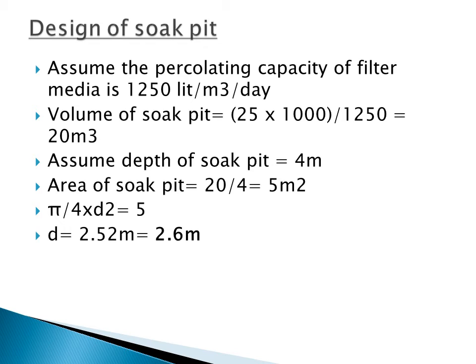The last part is to design the soak pit. You assume the percolating capacity of the filter media as 1,250 liters per cubic meter per day. The volume of the soak pit equals the total tank capacity divided by the percolating capacity: 25,000 divided by 1,250 gives 20,000 liters, which equals 20 cubic meters.